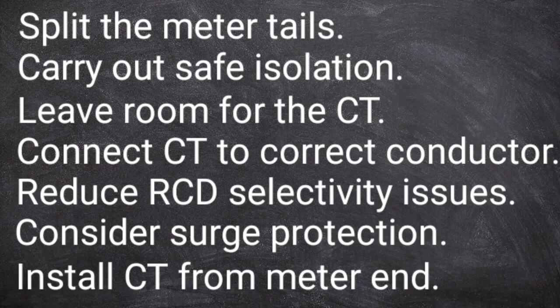Absolutely. Interesting point there about the screwed connections. So we wouldn't want to be using the lever type connections because some tests on this particular type of installation, a CT installation, have shown that they don't work quite as well as a screwed connection. So then you'd want to think about leaving that screwed connection somewhere where it's accessible so that you can get to that for inspection and testing. As an alternative to a screwed connection, you could also use a crimped connection. That would be perfectly acceptable. But whichever route you take, bear in mind that a good connection for your CT is absolutely critical. So it would be a good idea just to twist the wires together that you're joining before you screw them together or before you put the crimp in place.